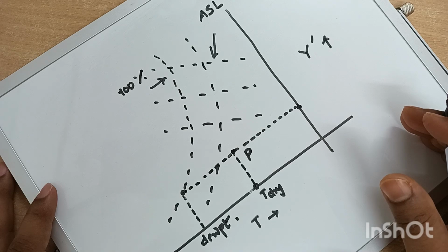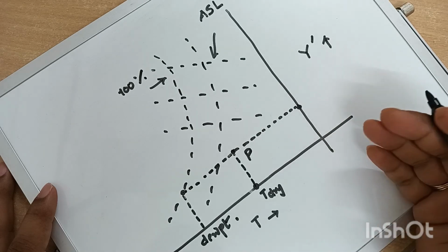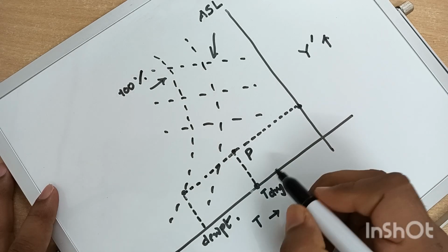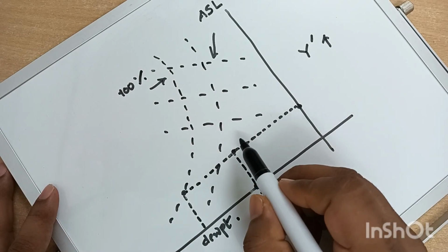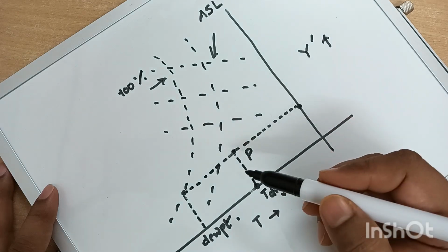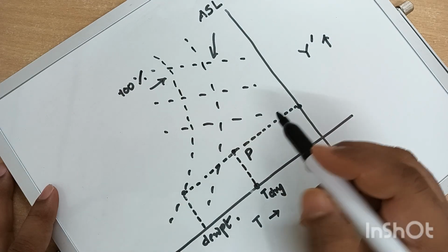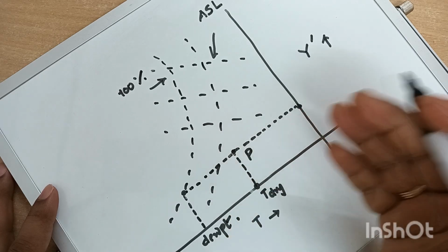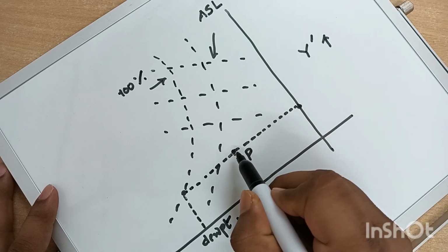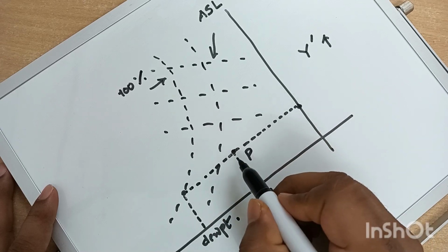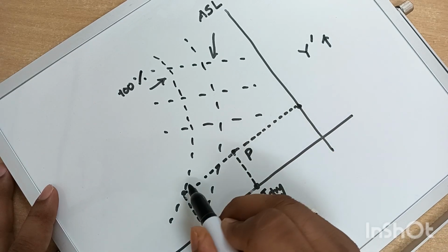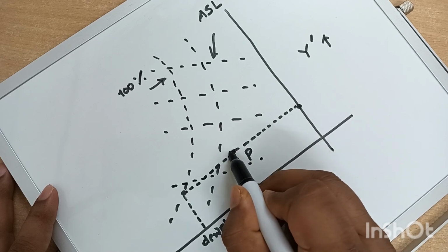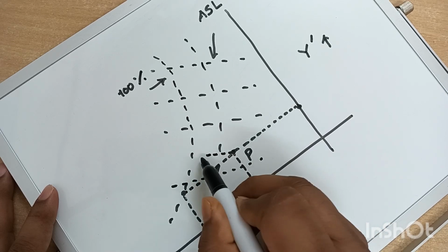And then comes the point where you need to find out the adiabatic saturation temperature. To find it, you have to trace a path corresponding to the adiabatic saturation lines that are already given in the psychrometric chart. Corresponding to the given adiabatic saturation lines, you can draw a line via linear interpolation, but a smarter way of doing it would be drawing a line parallel to the adjacent lines. Okay, so this is the line. Suppose another adiabatic saturation line is this one.